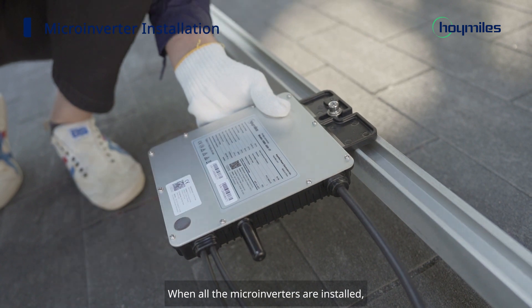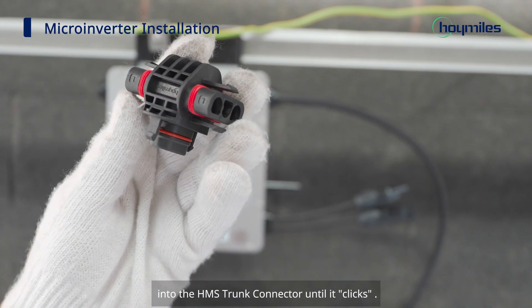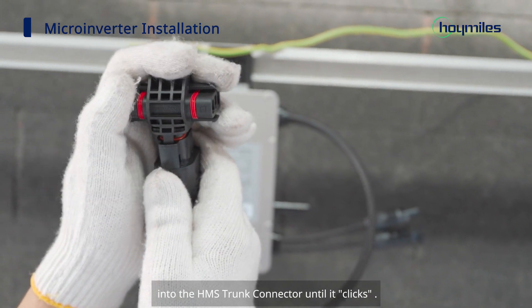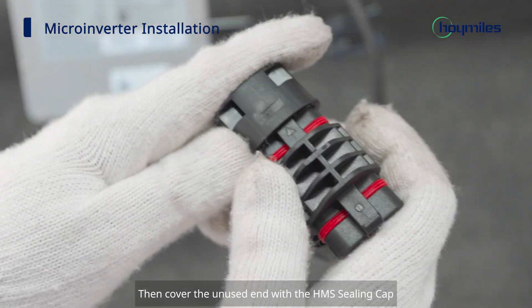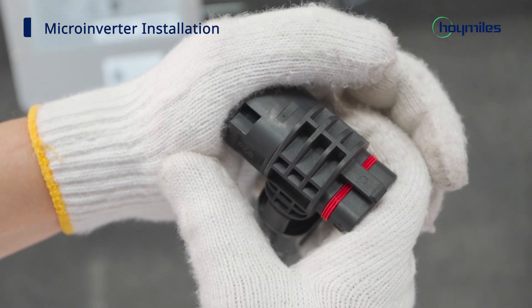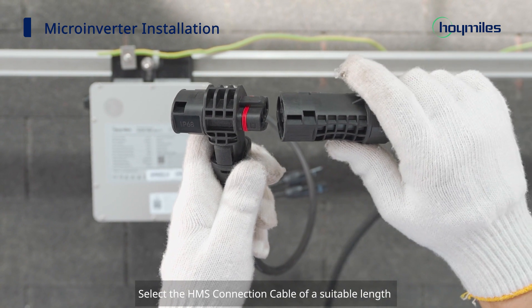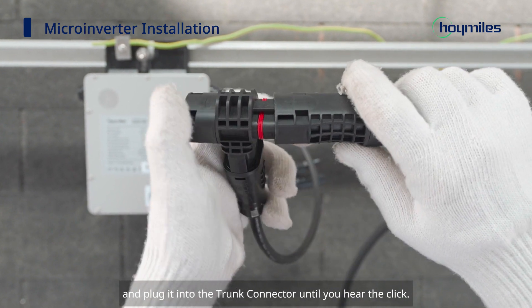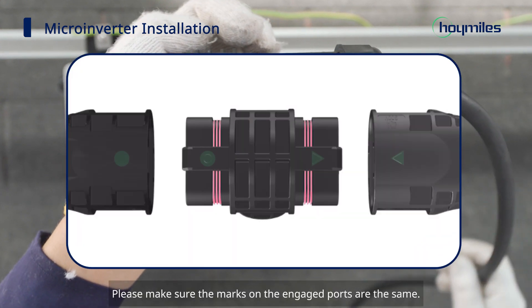When all the microinverters are installed, plug the AC connector of the microinverter branch into the HMS trunk connector until it clicks, then cover the unused end with the HMS Sealing Cap to make it watertight. Select the HMS connection cable of a suitable length and plug it into the trunk connector until you hear the click. Please make sure the marks on the engaged ports are the same.